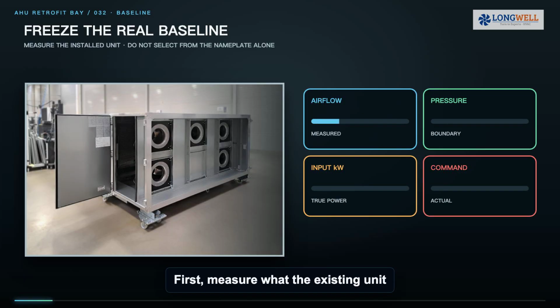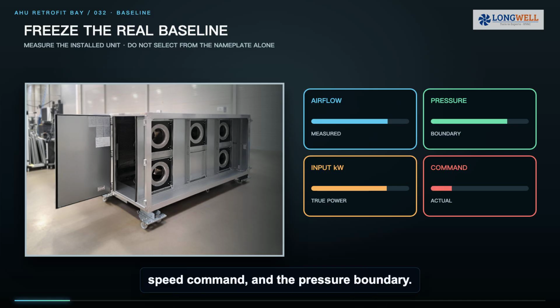First, measure what the existing unit is actually doing. Record airflow, fan static or total pressure, electrical input, speed command, and the pressure boundary. Add the operating schedule, filter condition, and any recurring noise or maintenance problem. A nameplate is useful, but measured duty is the starting evidence.